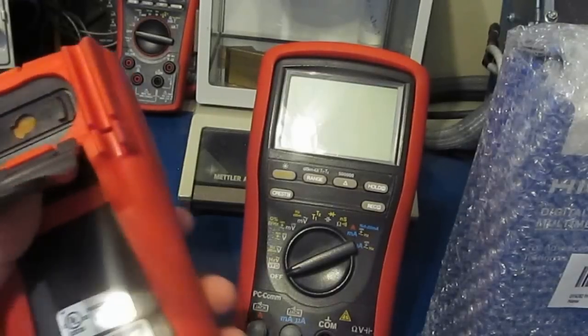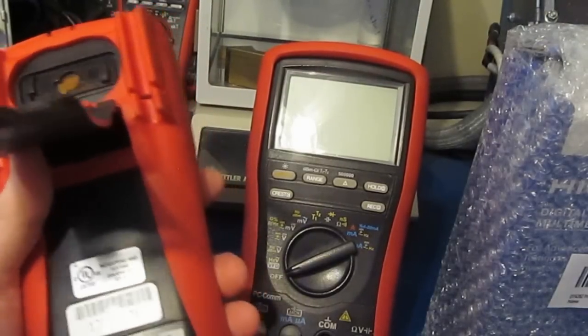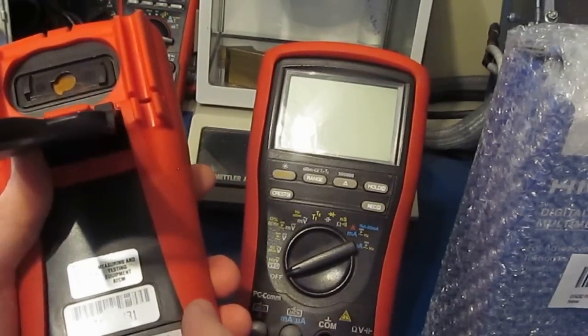This particular meter had been damaged at 10,000 volts peak with a 50 microsecond full width half height. I also changed the clamp transistors in this meter, and I ran it up to 14,000 volts and it passed.